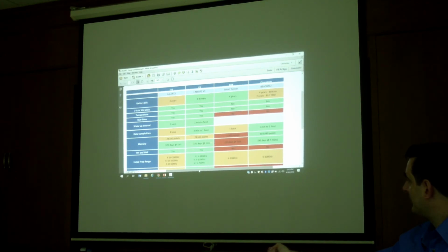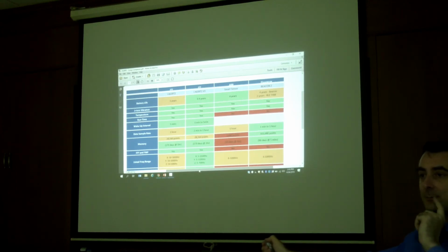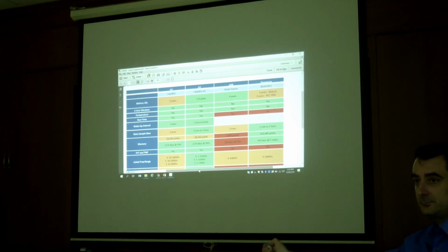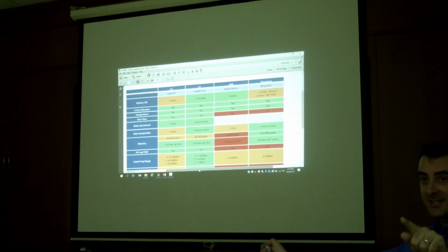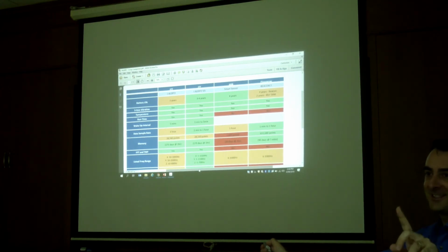This memory needs to be compared at 1 hour. So these battery lives are compared at 1 hour data sample rate. But we still check every 5 minutes. We check the alarm every 5 minutes. We record every hour. For the data sample rate, I can change it in the app, right? Yep. And when you change it on the app, it warns you about the battery. If you make this setting, your battery life is expected to be 2 years, so no customer is allowed to complain.